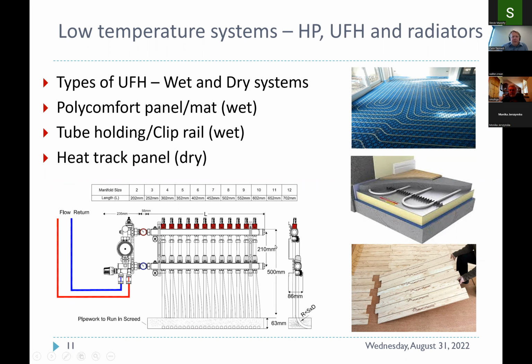This is a typical scenario, a manifold that we use with all underfloor heating systems. You will have, if required or not, depending on the temperature, a mixing station sending out to the manifold. So by the mixing valve here and the thermostatic head, you can control and set the temperature. And then you can pump directly through it, typically with isolation valves with thermometers built in, so you can see the temperature going out. You have your flow meters, and then you have actuators at the bottom. This is basically an actuator and a valve, so it acts like a little motorized valve controlling the individual loops, and then depending on how much heat we want to put in a particular zone, we control the flow of water going there as well.